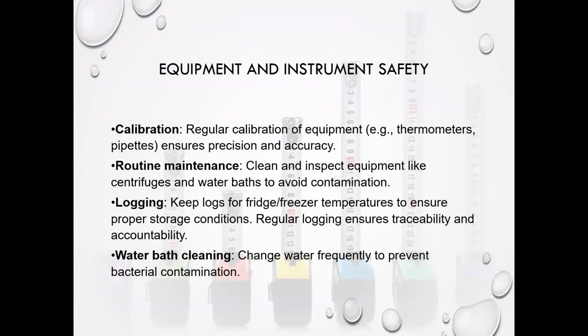All equipment and tests in the laboratory need to have the calibrations and maintenance records performed. This equipment includes anything from our timers to our thermometers, our centrifuges, or just our actual testing equipment. Our timers should be checked yearly to make sure that they're accurate, as well as our thermometers should be checked against the standard. Any weight scales that we use should be checked daily before we use them to make sure that they're still weighing properly.